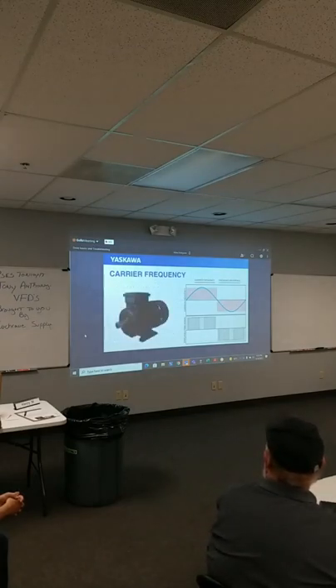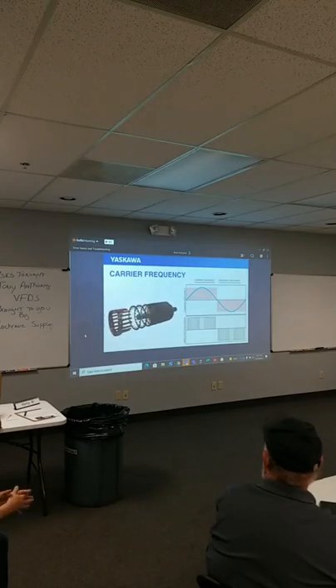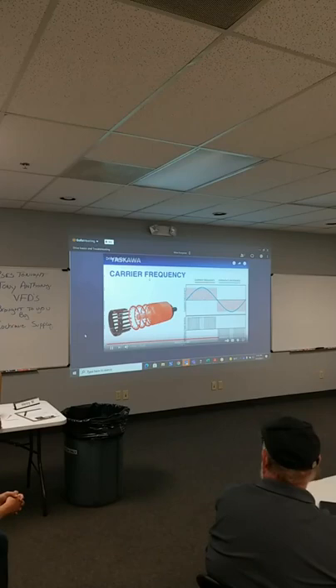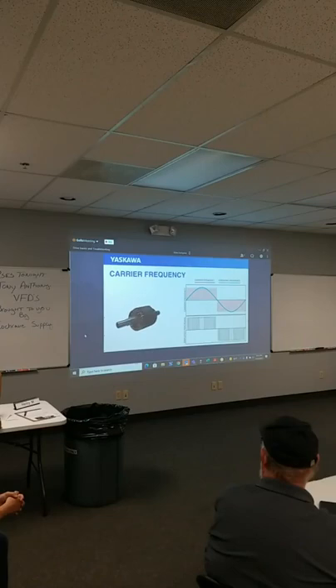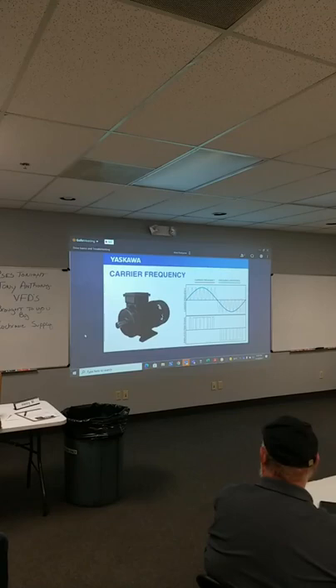It's interesting to know that the reason a motor is louder when connected to a drive versus across the line is due to this switching frequency. The stator laminations in the motor vibrate, causing this audible noise. Increasing the carrier only brings that vibrating frequency to a level that becomes difficult for us to hear. And this leads to less audible noise and a quieter motor. Decreasing the carrier will lead to the opposite characteristics. That is, there's more audible noise, but the IGBTs don't have to work as hard. As a result, we have a cooler running drive.